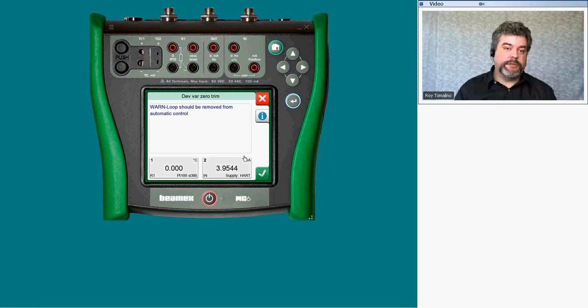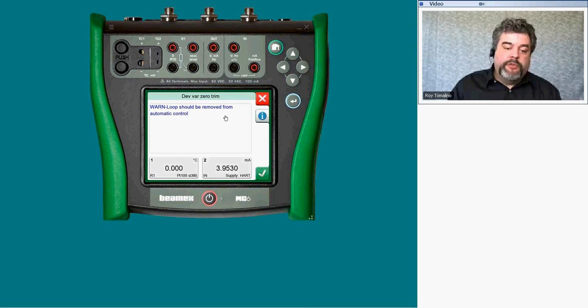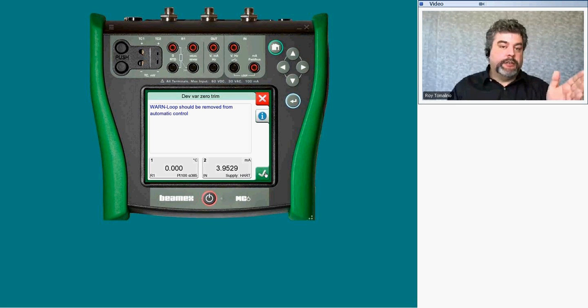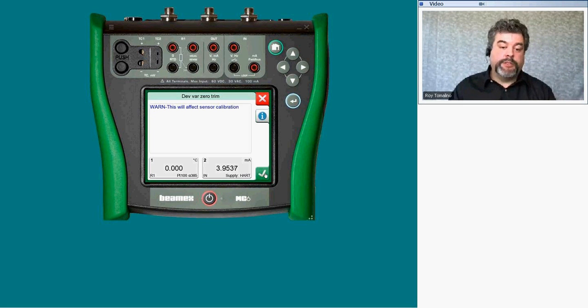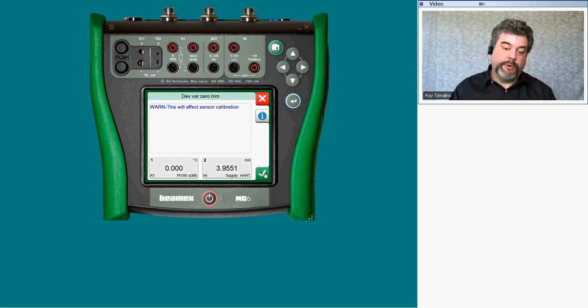We'll click online — this is the same structure you would see on your communicator, we just happen to see it on our calibrator as well. All the green values are measurable variables. Let me click on device setup. If we wanted to rearrange variables or change the tag name, damping, or other settings, we could go into setup and make those changes. But our goal here is to trim it — so if we go to diag service, the next area is calibration. Every manufacturer tends to be different, and sometimes even different models within a manufacturer can be different, but there are similar screens you'll navigate to. The first thing we'll do here is zero trim. If we remember our test results were in a straight line below zero, so we have a zero trim problem — on an old instrument we'd just grab the zero potentiometer and start tweaking.